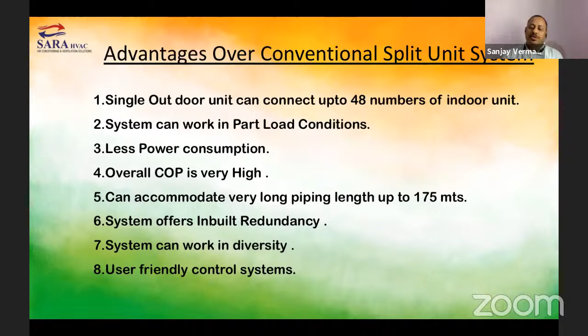Work on a direct expansion mode, no intermediate mode of cooling, higher operating efficiency, no accessories like pump etc. are required. In the case of air-cooled chillers or water-cooled chillers or central plants, we need to install the secondary systems, which is a primary pump, secondary pump, or maybe in the case of water cooled, the cooling towers and many other systems. So, the intermediate mode of converting the standard water to the chilled water, then this goes to the medium of AHUs.